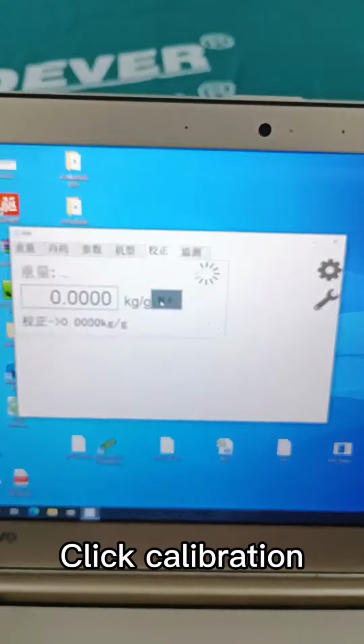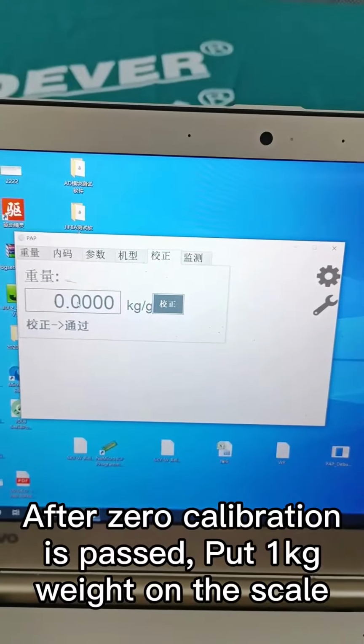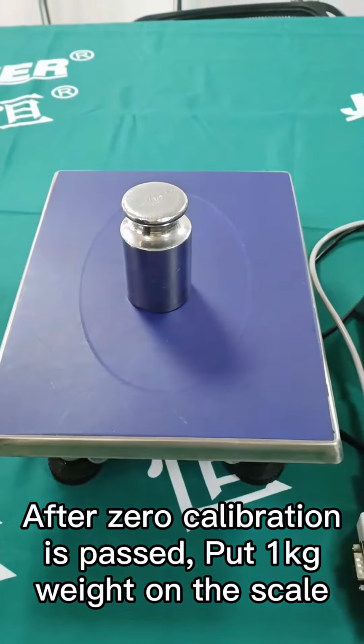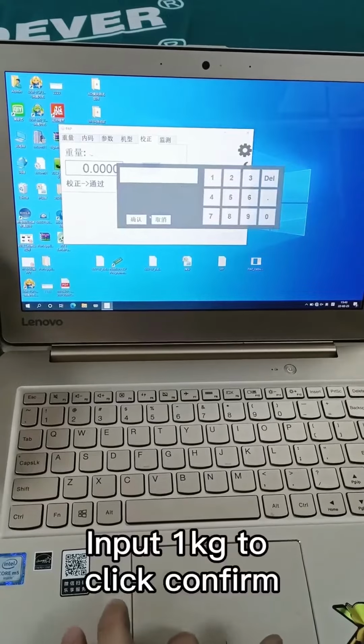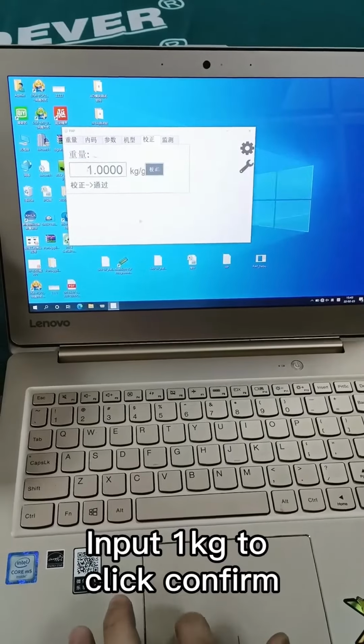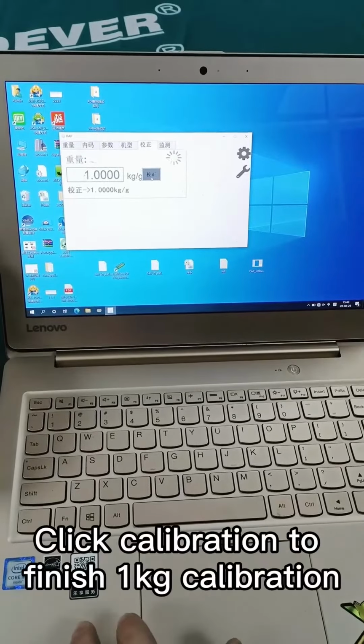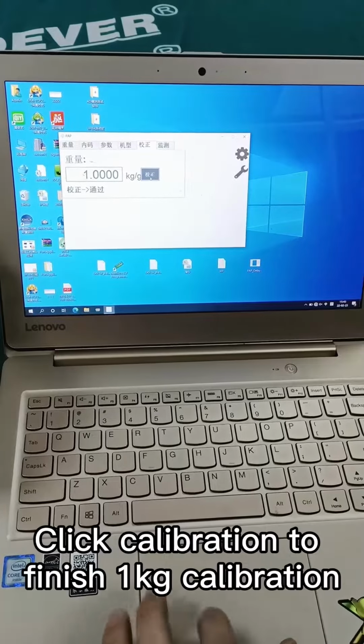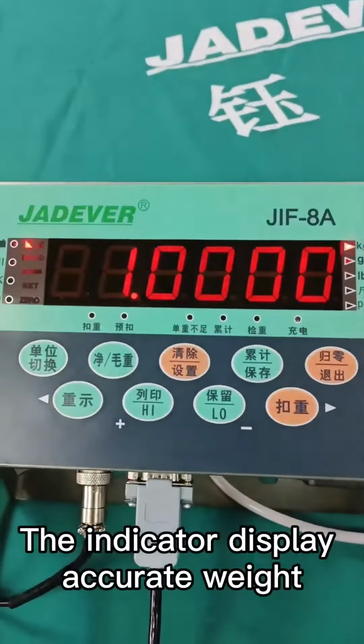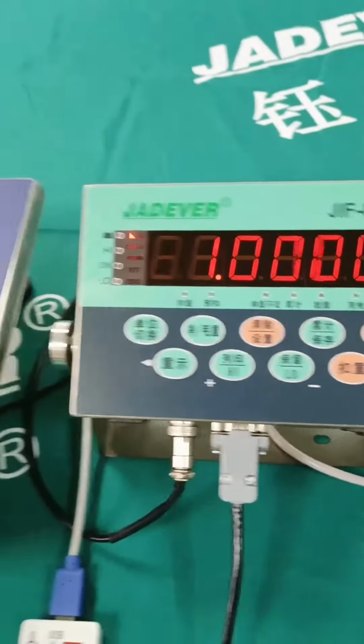Click Calibration. After 0 calibration is passed, put a 1 kg weight on the scale. Input 1 kg, click Confirm. Click Calibration to finish 1 kg calibration. The indicator displays accurate weight.